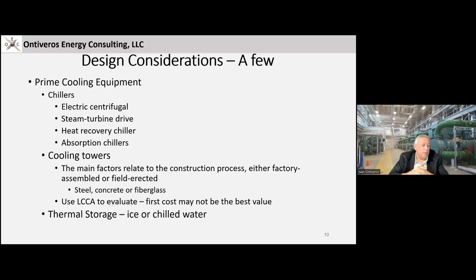Cooling towers are very important. You'll need a cooling tower to be able to run a steam turbine because you've got to be able to condense the steam. You also need a cooling tower for cooling. So the main factors related to cooling tower selection: is it factory assembled, prepackaged, or field erected? In other words, designed specifically, like the tower that you saw for that 15,000 ton plant. Was it a fiberglass tower? Our choice was to pick the tower that had a 5-degree approach, because that has very significant improvements to the chilled water production efficiency. But there are other options also: steel, concrete, or fiberglass. So those are different options to consider.